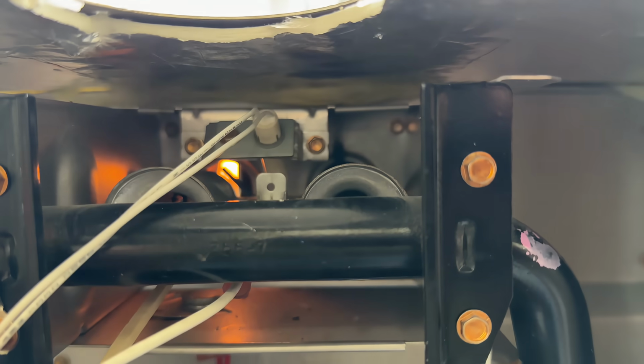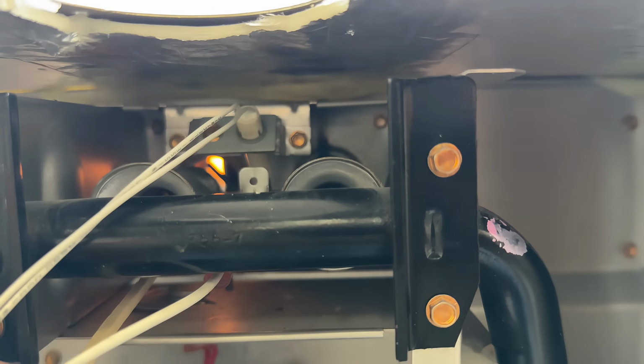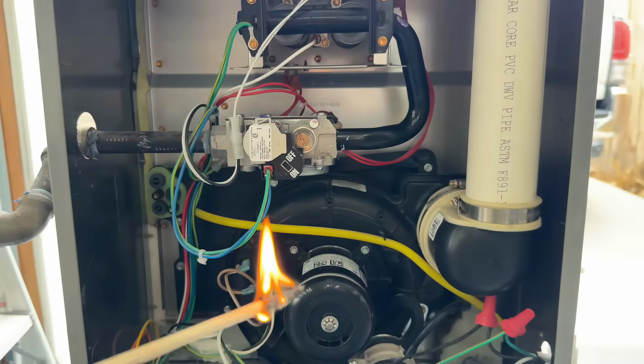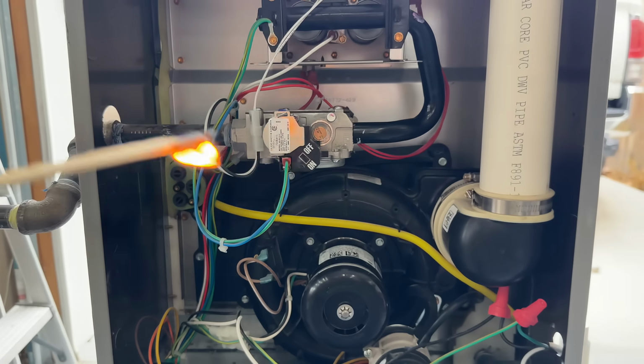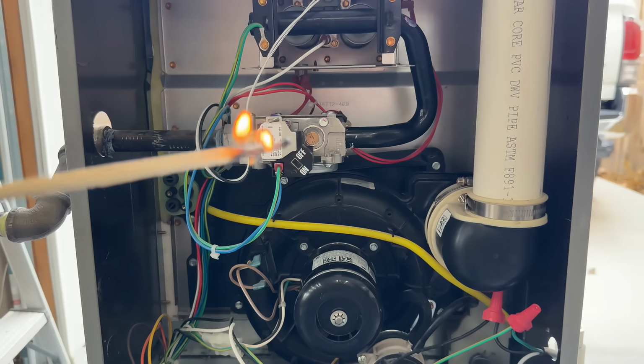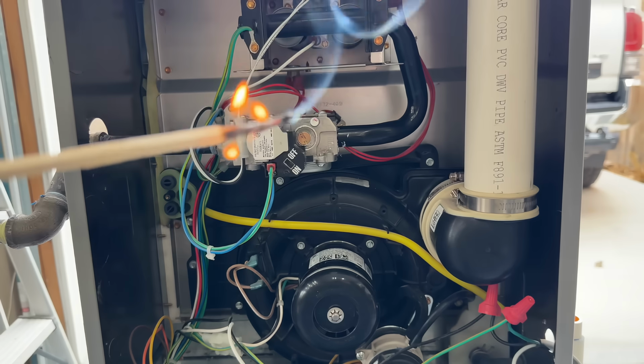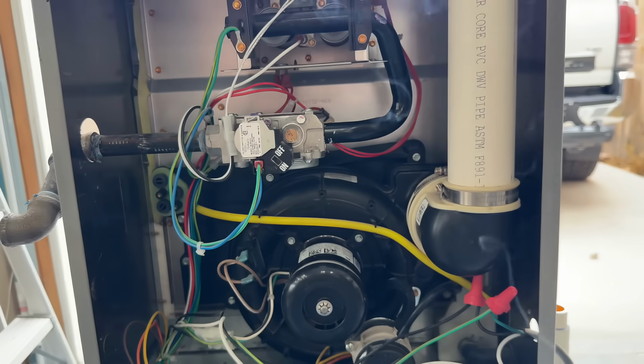So we want a flame like that. We don't want any movement. And that's exactly what we're looking for. Now, if we put this in the heat exchanger and it's just fluttering everywhere, that means that there is disturbance in the heat exchanger from the blower motor.